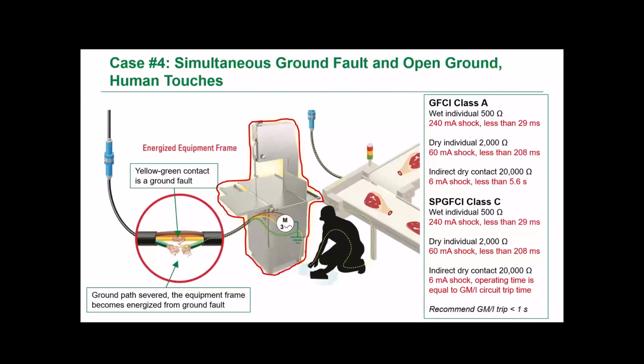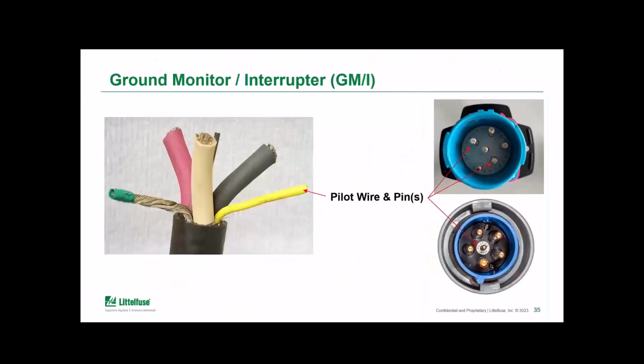And even though that 6 milliamp current is below the pickup level, the device is still engaging and responding and reacting and turning off the power quite quickly. So the net result is still to remove the hazard faster than what the Class A GFCI would in that case.